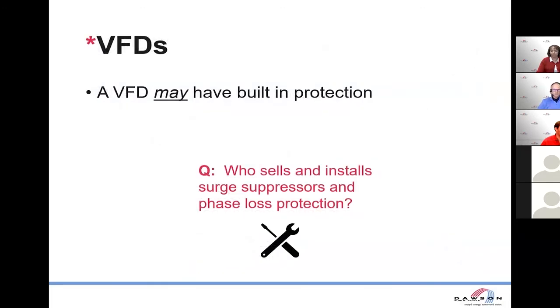Okay, so many VFDs will have protection built into them, but some of the more common pieces of equipment that would protect that VFD, as Cole said, that's basically just a computer sitting out in the middle of the field. So add a surge suppressor. Your local electricians will have access to this device. It's a very common device. It's also used in your homes quite often. So either talk to an electrical distributor, but go directly to an electrician or whoever does work on your equipment. They'll be able to help you with that.